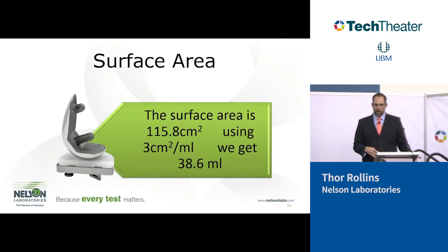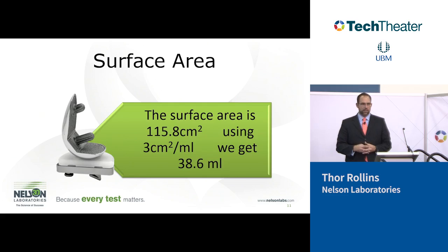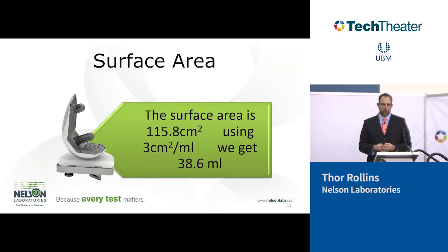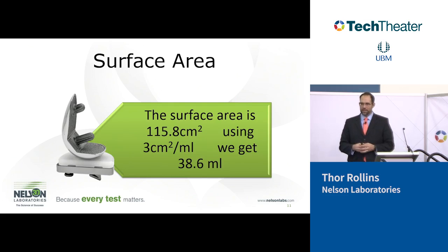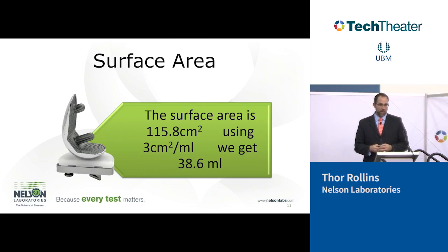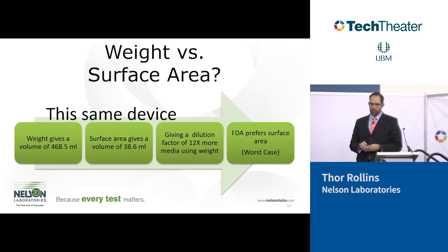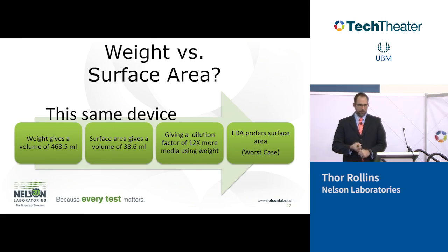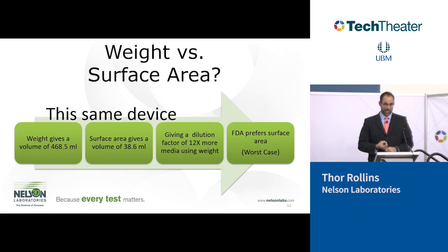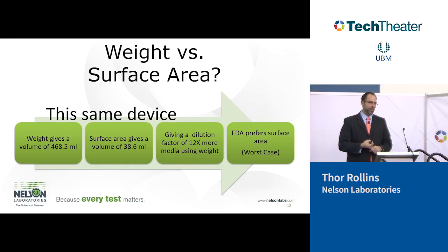Compare that to the surface area option. The surface area of this device is 115.8 centimeters squared. The ratio we would use for this device is 3 centimeters squared per mL. So the same device, using the same chart, the same standard, we would extract in 38.6 mL. You guys see the problem here? With weight, we added almost 500 mL. With surface area, we only added 40 mL, which means the weight ratio would be 12 times more diluted than surface area, okay? What that means is that you'd probably pass the test with weight, and with surface area you'd have less of a chance to pass.